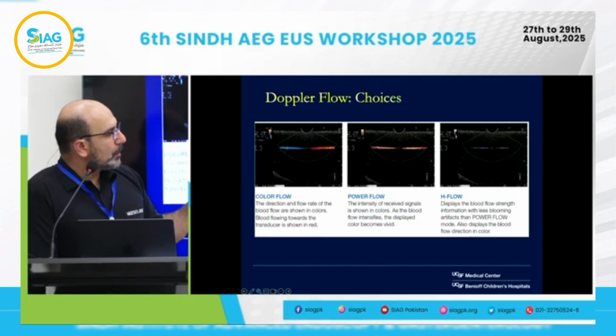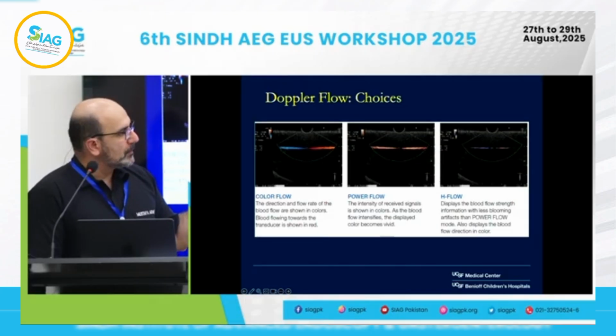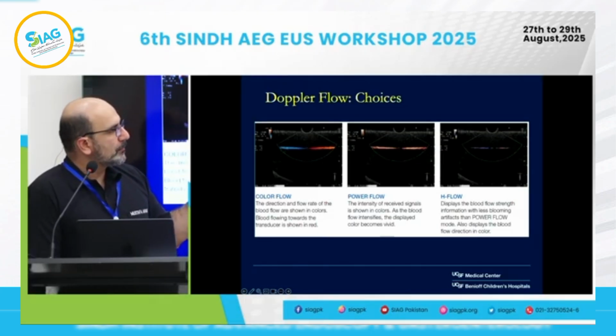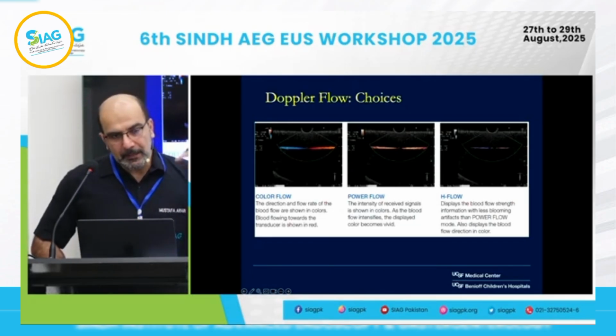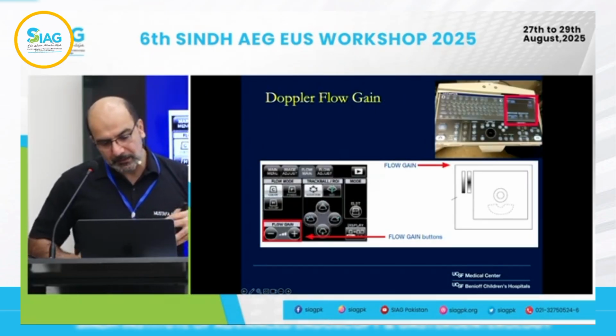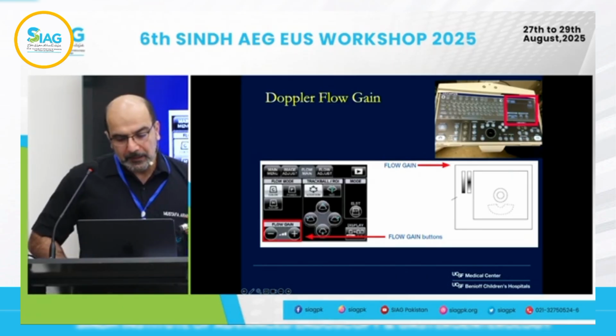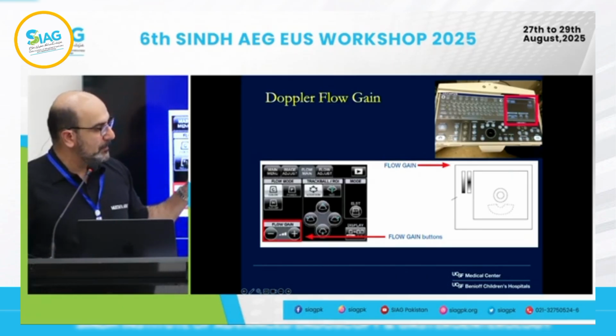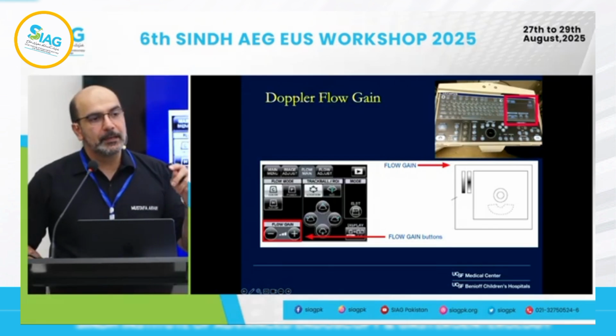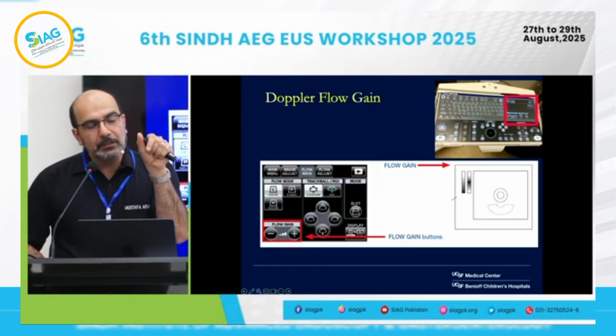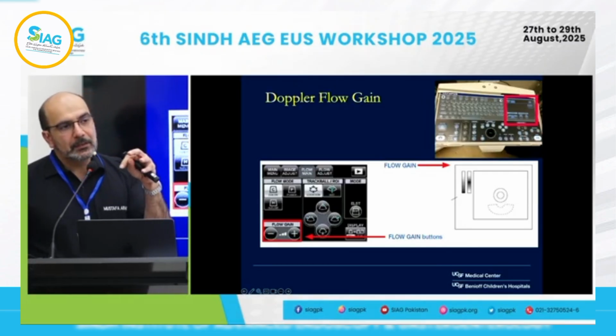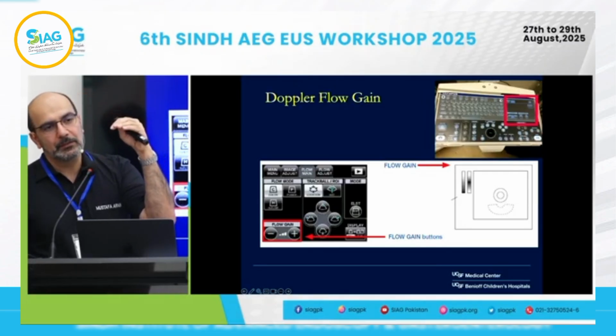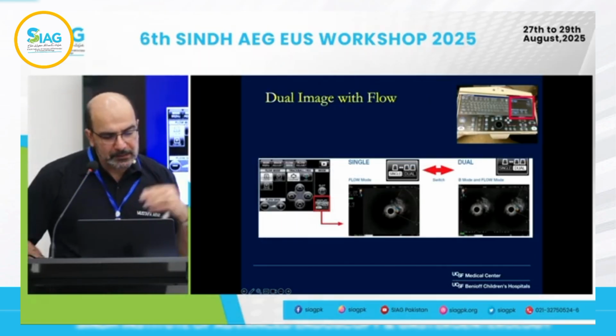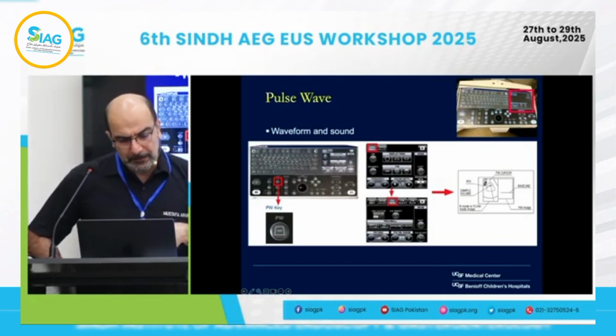Power flow is a much stronger flow, which is not really color determined. And H flow is like a mixture of these two, where it still shows directionality, but it's not as strong as power flow. Sometimes when you're not sure, you may want to go with power flow, because it'll give you the strongest signal. But bottom line is, you have various options. The more options that you have, the more confusing you can get. The other important thing is, sometimes the gain on the flow needs to be adjusted. So you may see that there's no blood flow, but it's actually because the strength is too low, so you may have to increase the gain. If you're in doubt, you can always increase the gain, to make sure that it's a true zero flow situation and not a false zero flow situation. So these things we'll go over as we go through these. I won't belabor this.